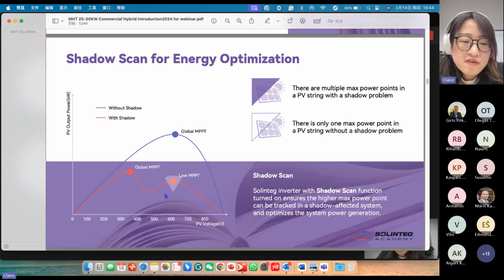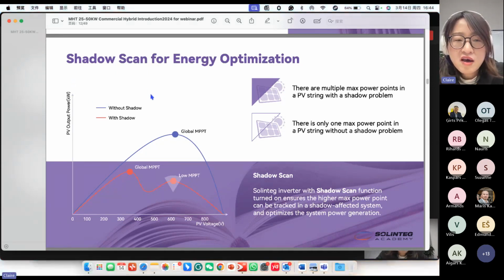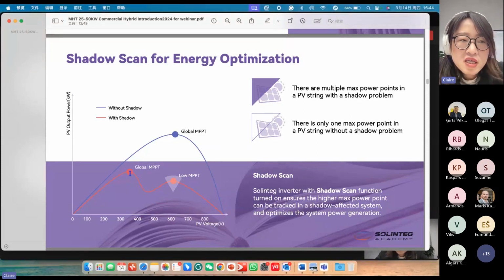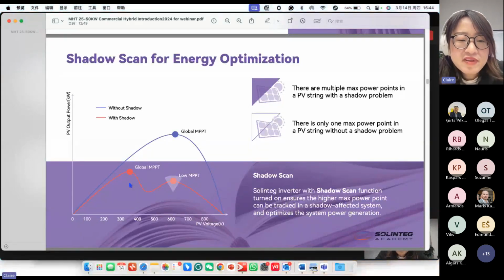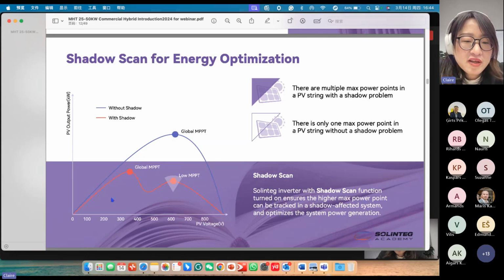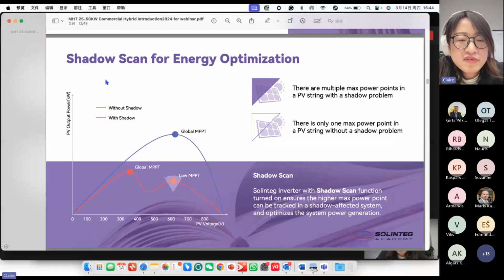But for the Solinteg solution, the customer can turn on the shadow scan function on the display or the application. After this function is turned on, the inverter can automatically search for the global MPPT every 5 minutes or 10 minutes or 15 minutes. This depends on the customer's selection on the application or the display. So this can ensure the inverter always tracks the global MPPT in the shading situation, and will have more power generation compared with others that don't have the shadow scan function.